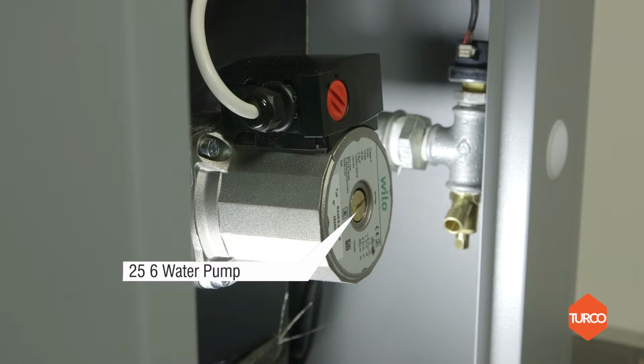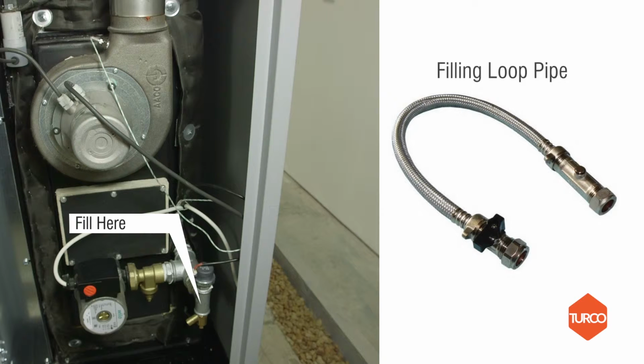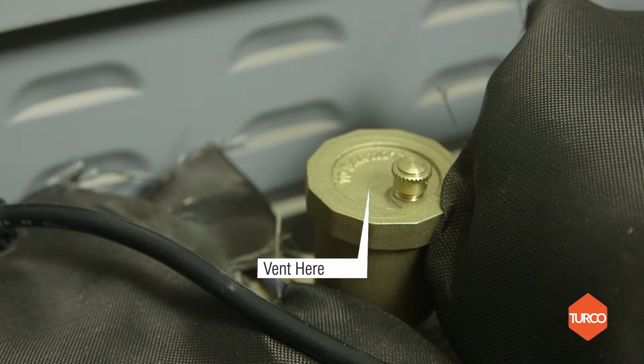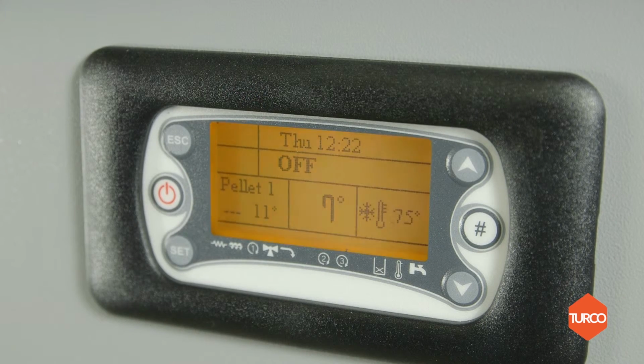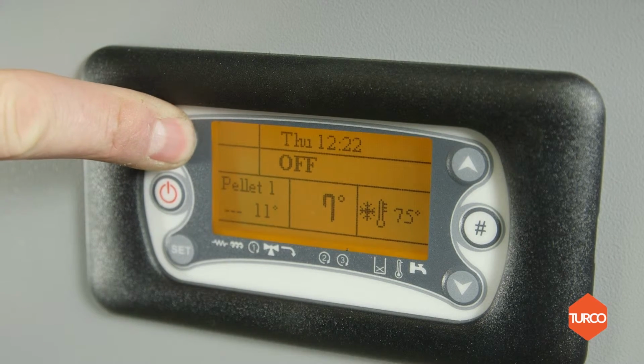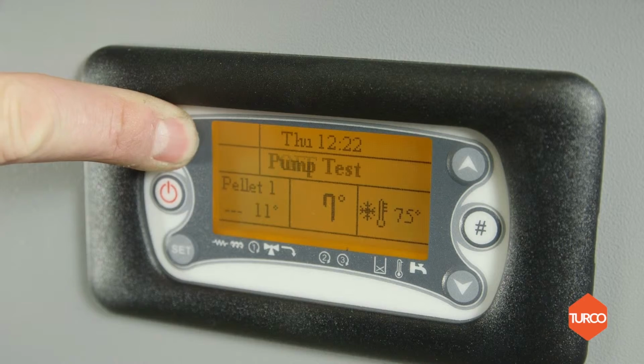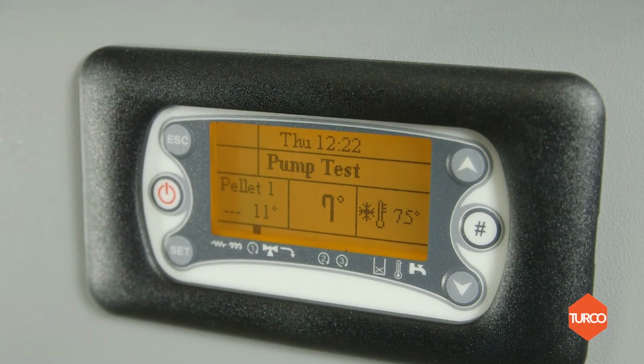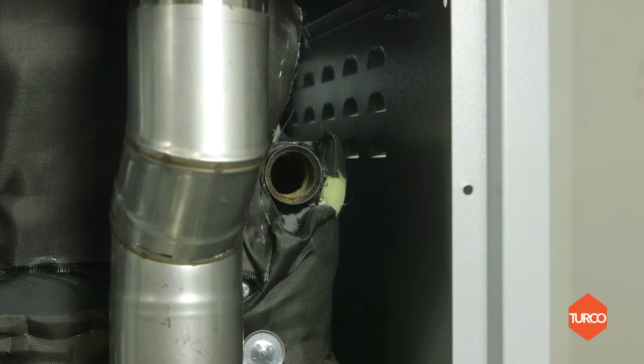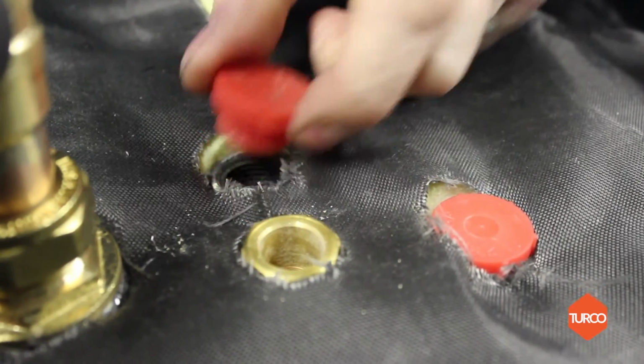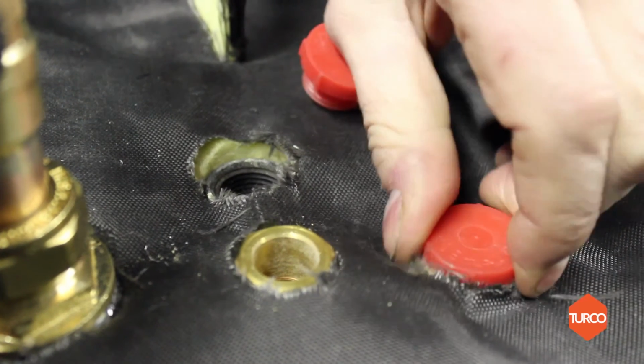The boiler is fitted with a standard 25/6 pump. The system should be filled from the lowest point on the heating system to force the air to the highest point where it can be vented. To de-aerate the system, hold the escape button on the controller for 3 seconds to activate the pump. Repeat the procedure and turn off the pump. Always ensure the fittings are tight and sealed when filling the boiler. Remove any red caps and blank with plugs if not used.